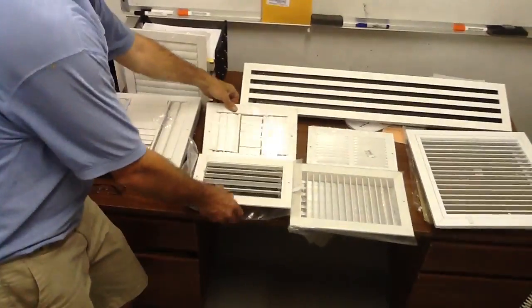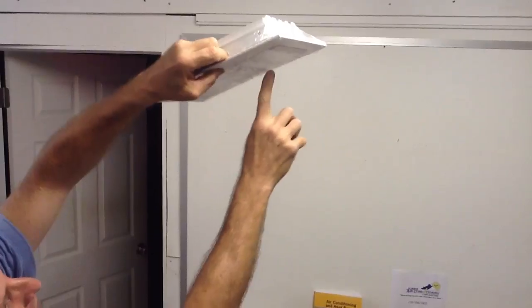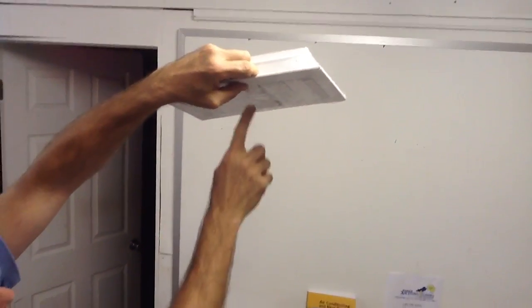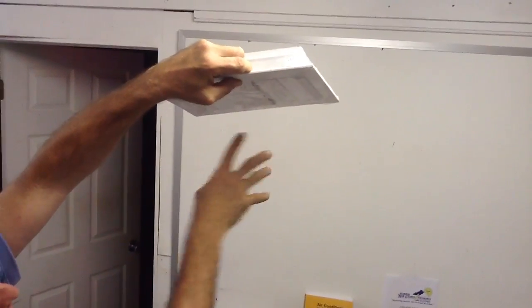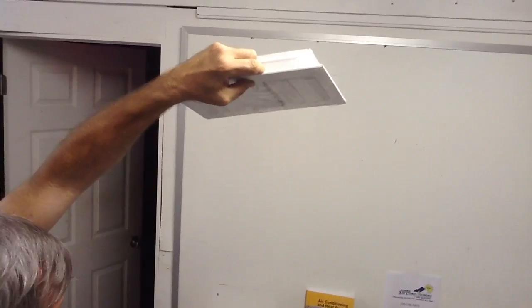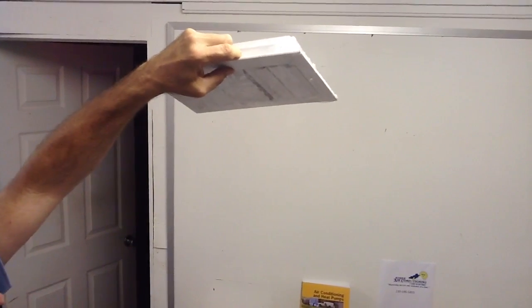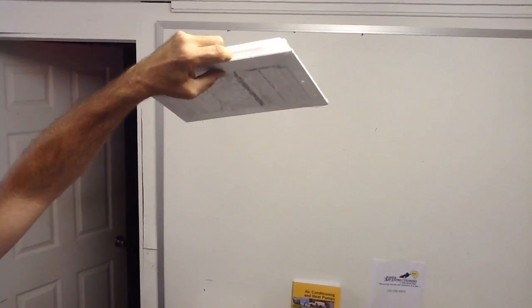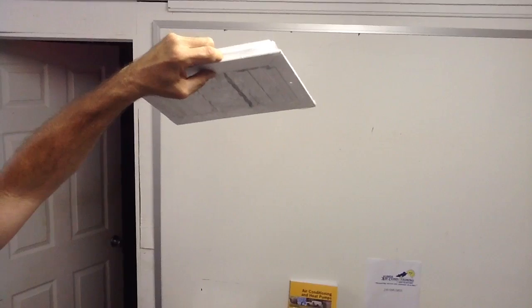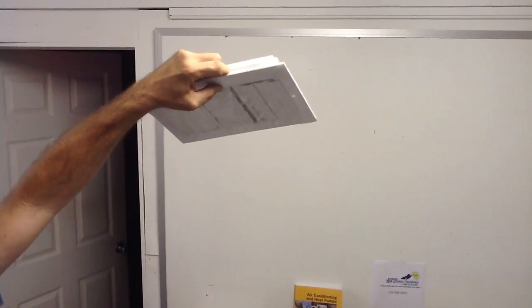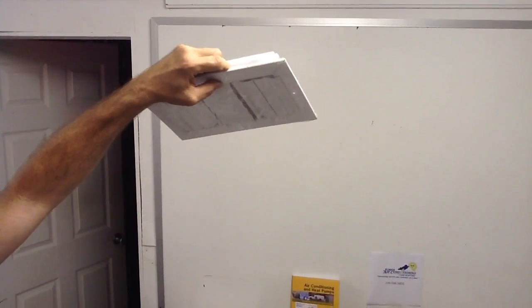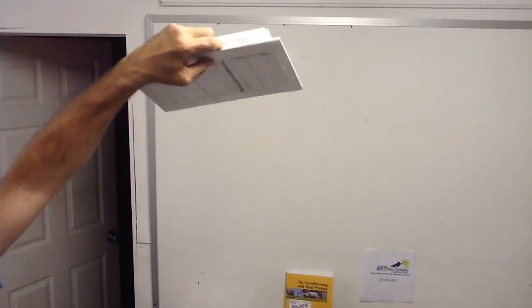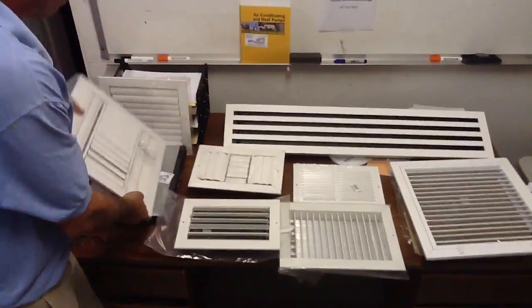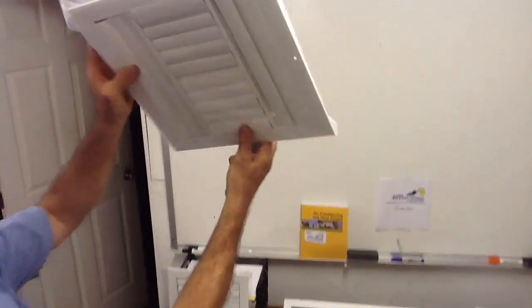Well, they have a grill for that. Here's a 10 by 6 three-way grill. So if you look at it, you see how the diffusers go side to side and one goes out. So it blows the air in three different directions. They make them in sizes from 10 by 6, 12 by 8, 10 by 10, 12 by 12, and that's about as high as you normally want to get. You can go 14 by 14, but we rarely use those. Here is a four-way 10 by 10, just what I was telling you.